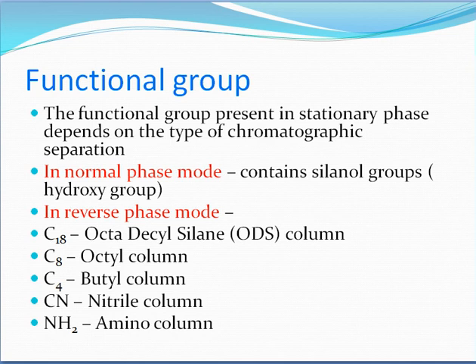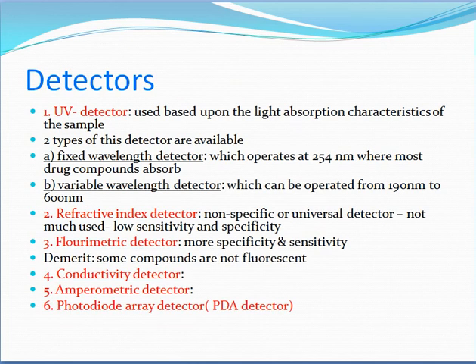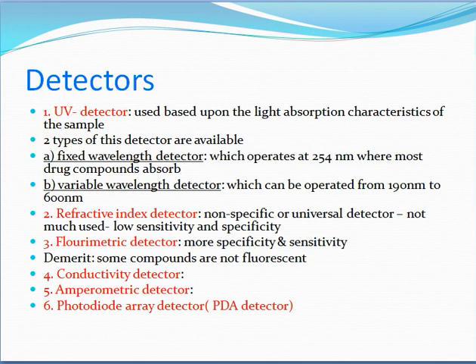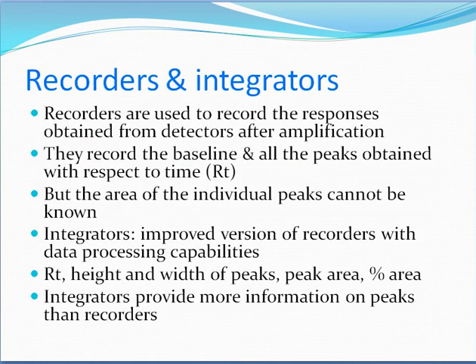Detectors used in HPLC include: the UV detector, based on light absorption characteristics of the sample. Two types are available — the fixed wavelength detector, which operates at 254 nm where most drug compounds absorb, and the variable wavelength detector, which can be operated from 190 to 600 nm. Other detectors include the refractive index detector, which is non-specific and universal but has low sensitivity; the fluorometric detector, which offers high specificity and sensitivity, though some compounds are not fluorescent; and conductive, amperometric, and photodiode array detectors.